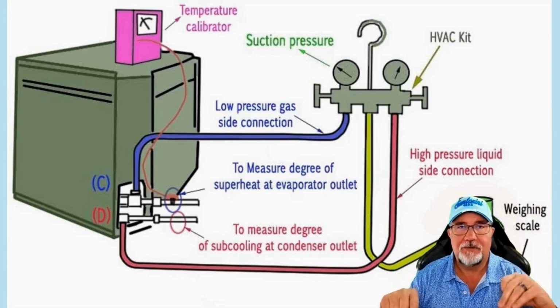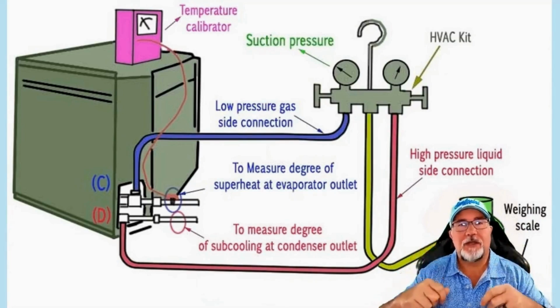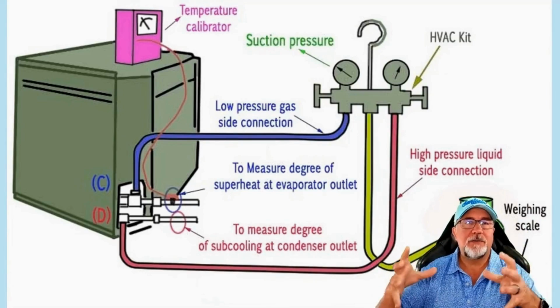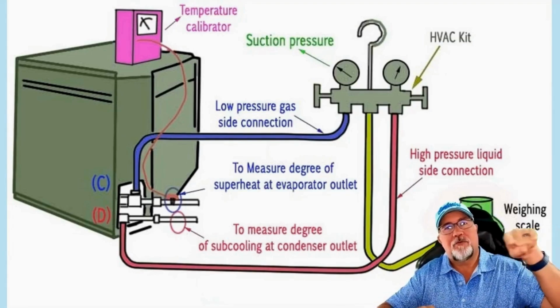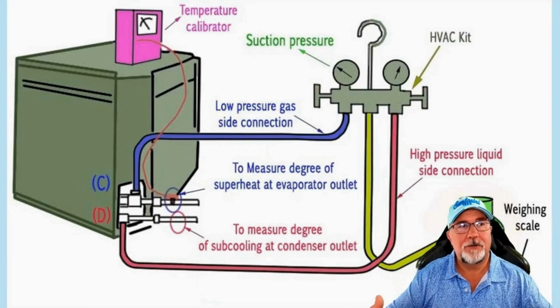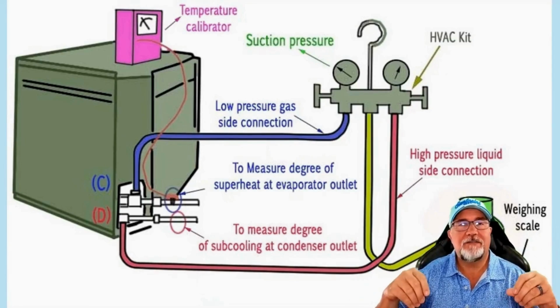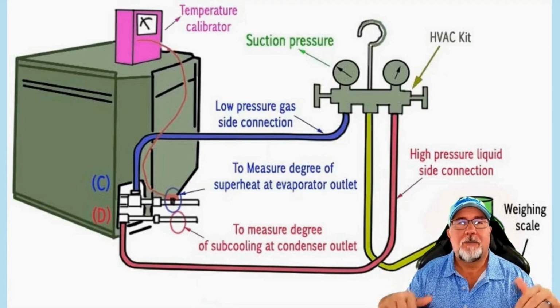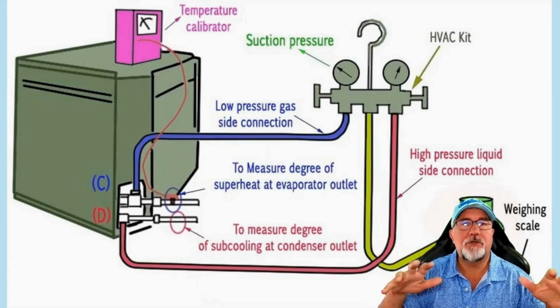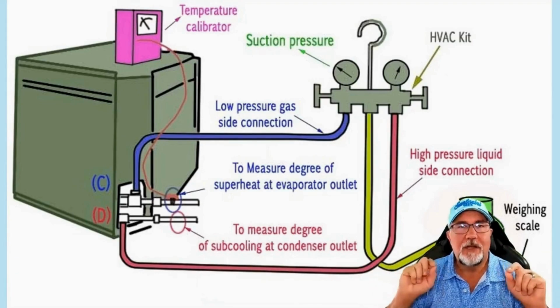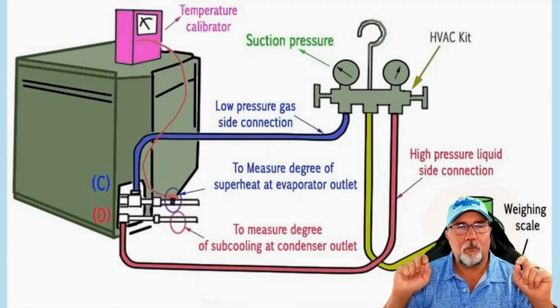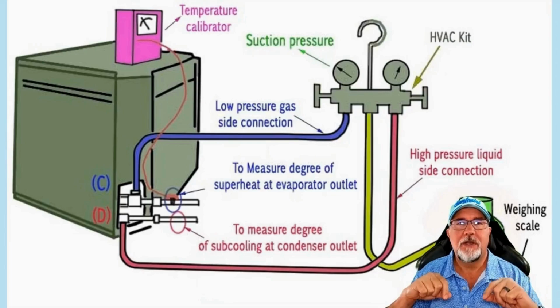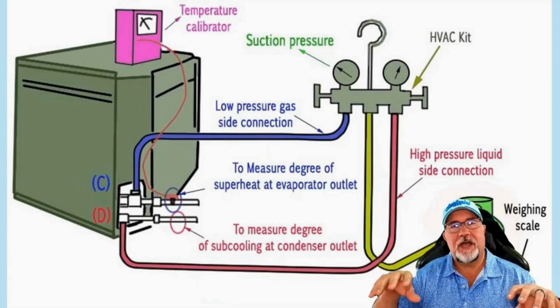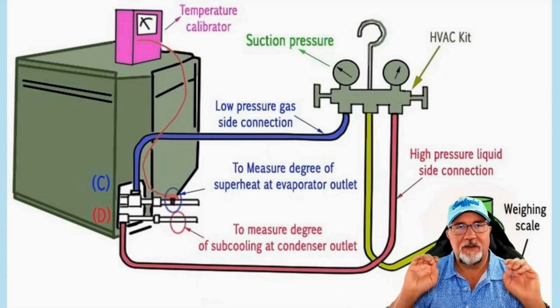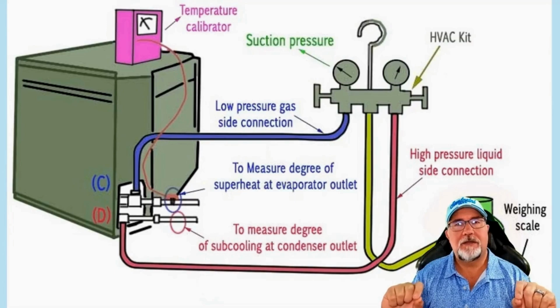I'm talking bigger stuff. So then they put their gauges on it and do what's called a vacuum. A vacuum is a machine that pulls the air inside the refrigeration lines down to below atmospheric pressure. And when it's below atmospheric pressure, anything that's a non-condensable would basically evaporate off. So if there's any moisture in there, it would evaporate out of the system. But we're not talking about that. Big dust particles and small rocks could have gotten in, and if they stay in the system, they are going to cause problems. So they need to make sure they're flushing those out, so that when it is time to charge, it is a very clean refrigeration line. Okay, it's important.